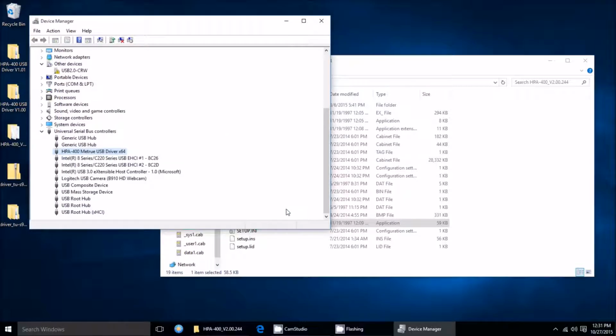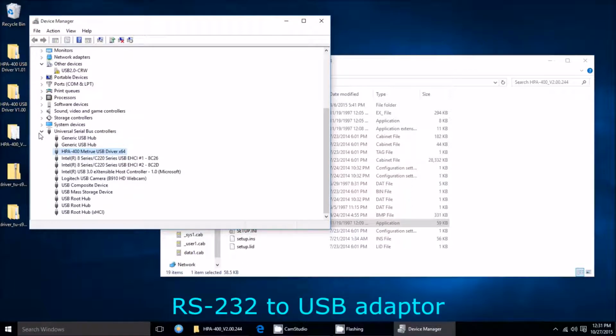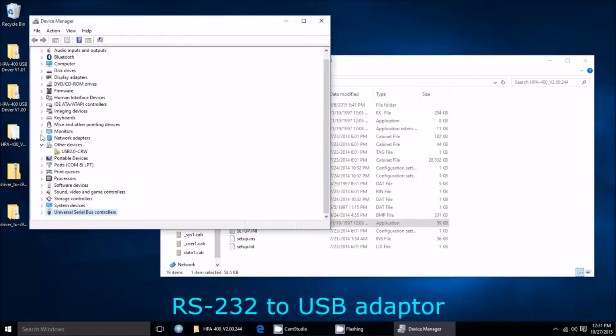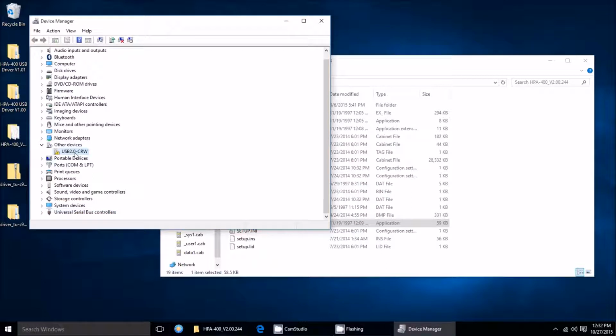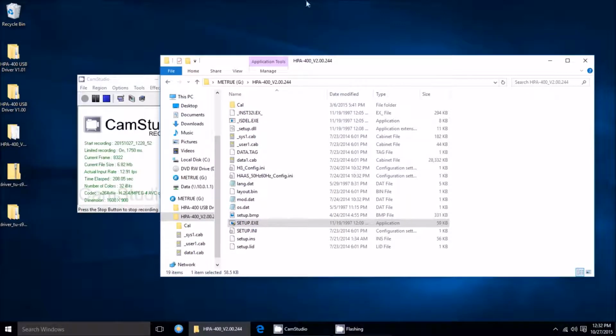So I'll hit close. You may also want to check for your RS-232 converter. If it's not working, it will also show up here. Actually, I'm not totally sure what this is because I don't have anything plugged in that's not working to my knowledge. And then the RS-232 converter drivers, since we don't provide the converter, we don't provide the driver, you will have to get that from the manufacturer. And typically you can find those on their website. So I'm done here. You can exit.